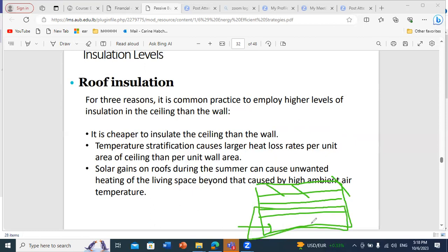Because the roof is exposed to high levels of solar radiation, it will receive sun rays directly, since this location has more chance of perpendicular rays facing the roof. This leads to high penetration of the sun's rays within your system, and this affects the stratification. It creates a very steep stratification within your space.